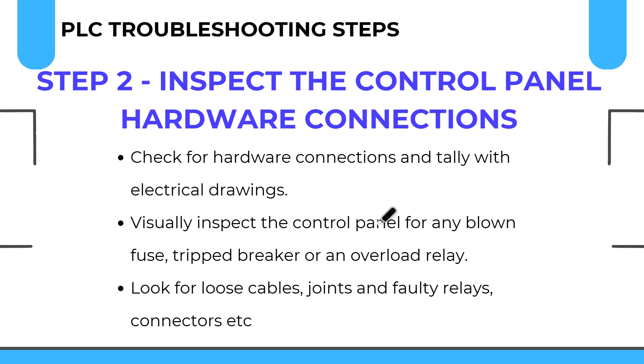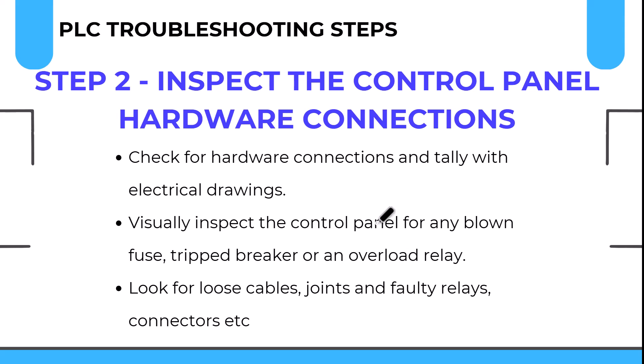Step two is to look at the visual status of the control panel. Visually inspect the panel and make sure there is no blown fuse, no tripped breaker, and no operated overload relay. Make sure breakers, fuses, and relays are in their normal state — connections are tight and fuses have not blown. Also look for loose cables, joints, faulty relays, and connectors. Make sure relay contacts are properly passing the signal.